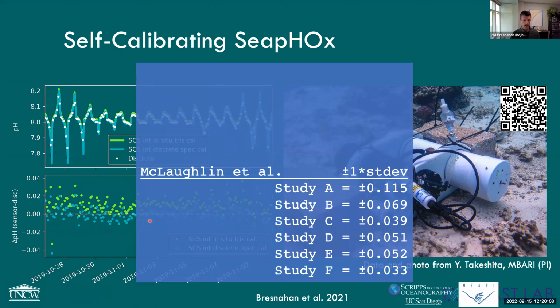And I'm showing some data in the background here. I don't want to get too deep into the data themselves, other than to show that a group of collaborators that Yui led out in Australia collected over 100 discrete samples, which would be this just remarkably large effort to try to refine the calibration on a particular sensor. Huge amount of work going into collecting those discrete samples and actually running them back in the laboratory. And then we compared that to what the in situ, self-calibrating SeapHOx autonomous calibration did.